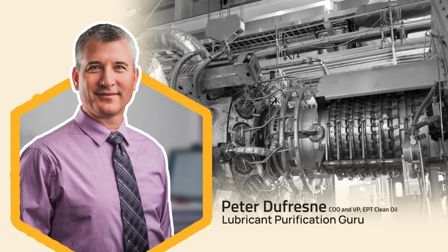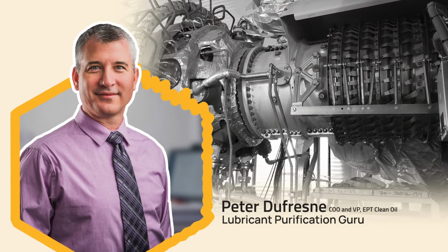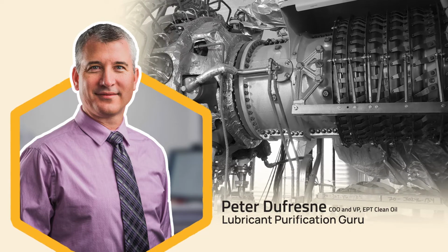I said, well, the ASTM standard, the governing standard for D4378, dictates the in-service guide for gas turbine lubricants. And it states that when a lubricant has lost 75% of its additive, and in conjunction with an increase in acid number of 2 to 3 times, that you would schedule that oil for replacement. So I said, what's your acid number? And the customer didn't know.